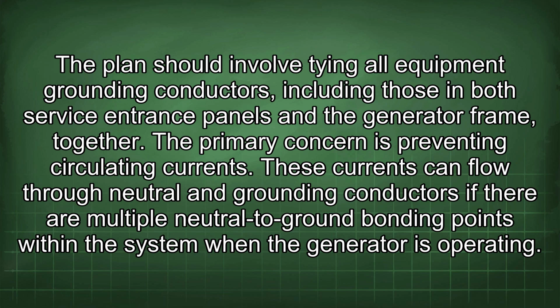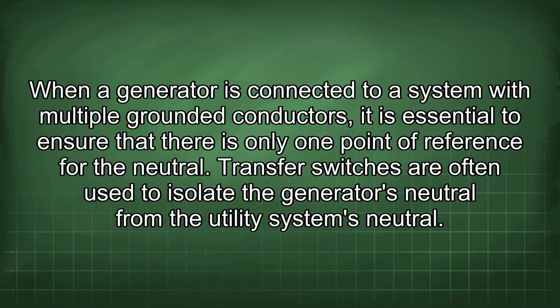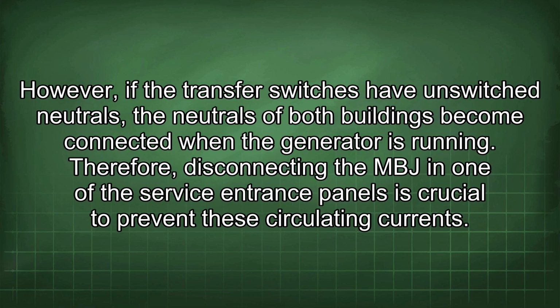These currents can flow through neutral and grounding conductors if there are multiple neutral to ground bonding points within the system when the generator is operating. When a generator is connected to a system with multiple grounded conductors, it is essential to ensure that there is only one point of reference for the neutral. Transfer switches are often used to isolate the generator's neutral from the utility system's neutral. However, if the transfer switches have unswitched neutrals, the neutrals of both buildings become connected when the generator is running. Therefore, disconnecting the MBJ in one of the service entrance panels is crucial to prevent these circulating currents.